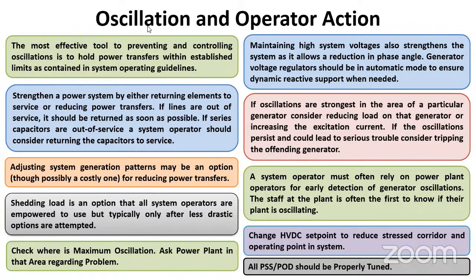One of the challenges for the system operator is to detect where the forced oscillation is coming from. If it's a local oscillation due to improper damping or PSS tuning, that can be detected because it's observed at the local level. But the problem comes with inter-area oscillation, where you know there's a weak interconnection, overloading, or tie lines that are tripped, causing the angular separation to become harder.